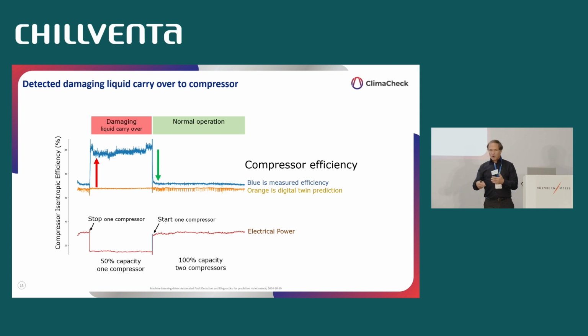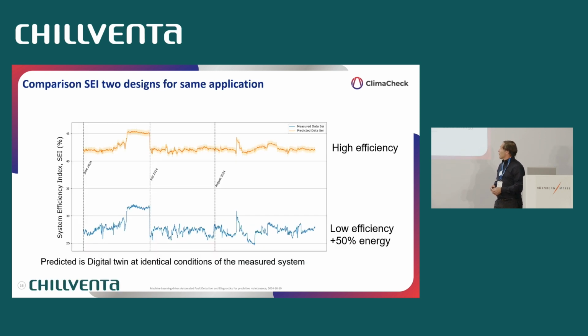You would get similar if you're running part load and the expansion device is not properly adjusted for operating at part load. You get the same problem for the compressor: the expansion valve becomes unstable, it throws liquid into the compressor, and you see it immediately because you get a fictive increase of compressor efficiency. So you can catch it when it starts occurring, fix the problem, and avoid compressor failures.